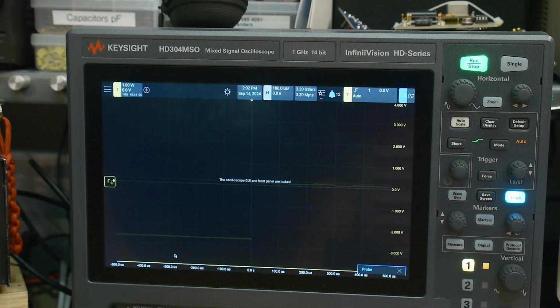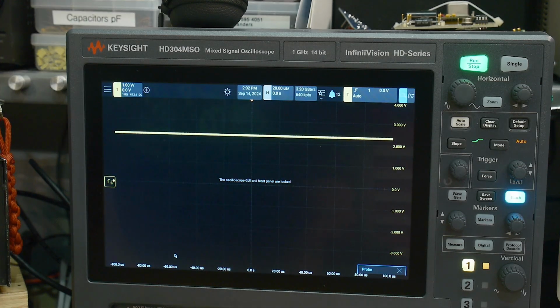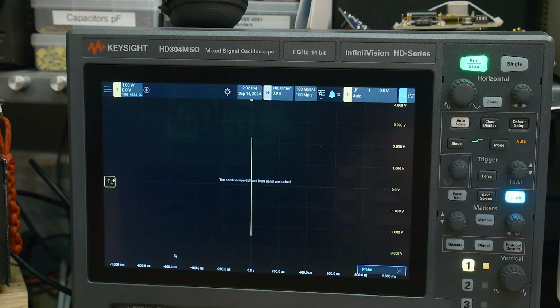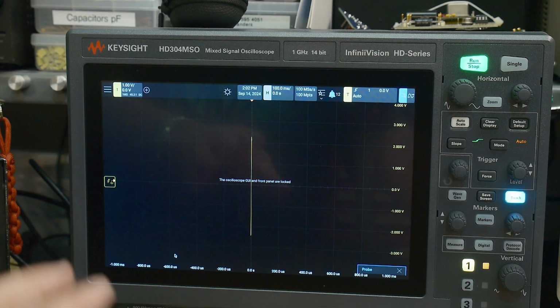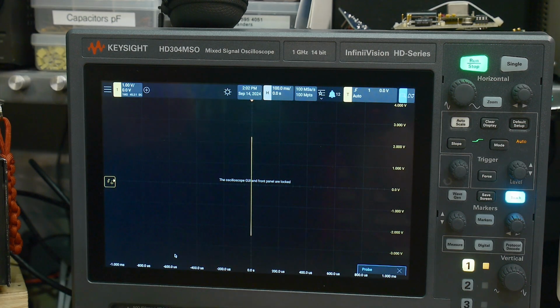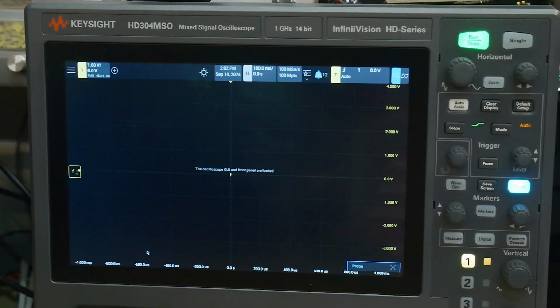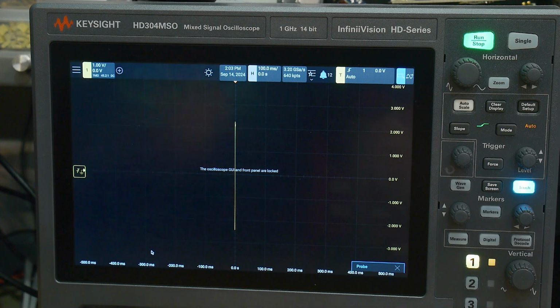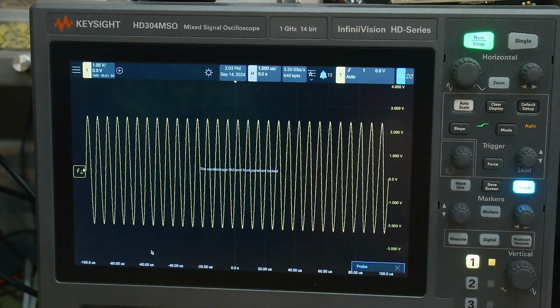And you'll see that it's starting to do a whole bunch of waveforms, and this looks like a full scope calibration of other oscilloscopes that I have. When you press the Cal oscilloscope button, it runs through all of these offsets and gains and channels, and it calibrates your oscilloscope, right? And that's built into this oscilloscope as well. But this has a probe calibration routine that just does the probe. And so if you start this up, and you see these repeating patterns, you think, oh, it's stuck in a loop and it's never coming out. And so you wait and you wait and you wait and say, well, maybe it's broken. Maybe there's something wrong. It takes 6.5 minutes to calibrate this probe. 6.5 minutes for a probe calibration. But you end up with a passive probe, it's not active, it's a passive probe that's calibrated at 1 gigahertz. First I've ever seen.